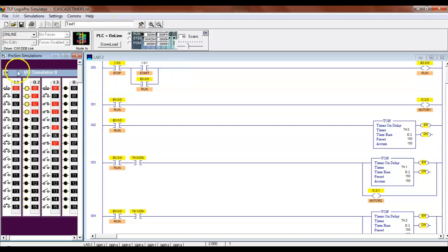And then of course, if they have to stop, they should all stop at the same time. So you'll see how I did that. I took this B3 bit, which is an internal coil. I didn't want to sacrifice one of my outputs, even though I got a lot of outputs on the simulator. We call these internal coils because they don't need to generate an output, but they act just like a real coil, right? I'll play around with that too. So that's it on timers.